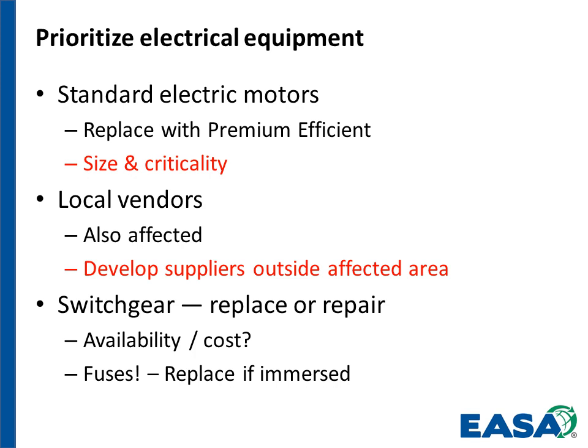Look at the size of the machines and the criticality. You may have a small motor that's relatively inexpensive and yet is highly critical to the operation of the plant. Conversely, in most plants you have machines that are large enough that there may be a year and a half or 2 years or even longer replacement time. So the delivery time may be 18 months, 24 months. So in those cases, obviously repair is going to be the more logical choice.